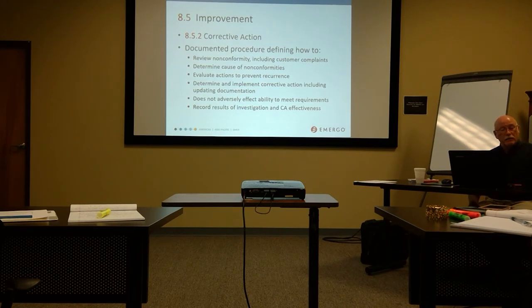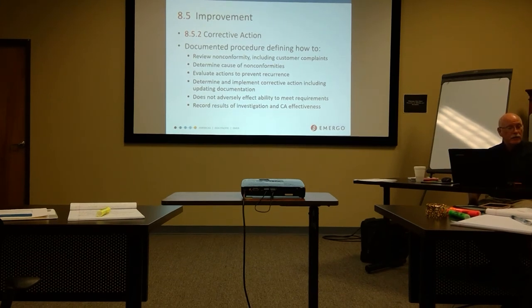Lots of different effectiveness checks can take a long time. You have a manufacturing issue, your fix says we're going to fix it, and effectiveness says we're going to monitor this for the next, let's say 6 products of this we make. If you make this once a quarter, how long is your effectiveness check going to take? 1.5 years - that's okay. So timeliness, when we're talking about timeliness and CAPA, we're talking about the front end of the process, not the back end. I've seen people write procedures saying CAPA must be closed in 8 weeks - bad idea. You have no clue how long these will take. You take whatever time they take to be done properly.